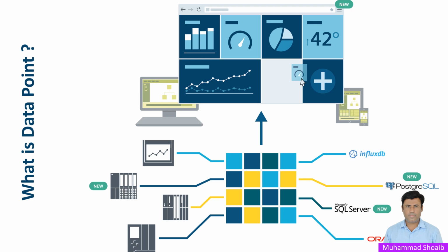WinCC OA takes a different approach. Instead of flat tag lists, it uses a data point. A data point is a structured, device-oriented data object that represents a real device like a motor, valve, or sensor. It keeps all related information together in one clear structure.